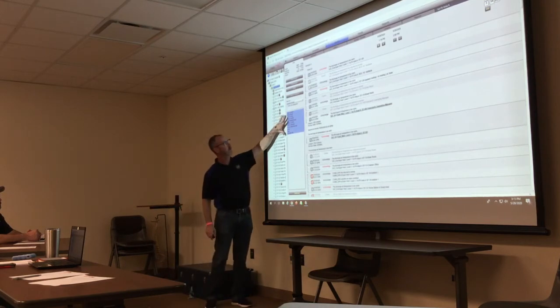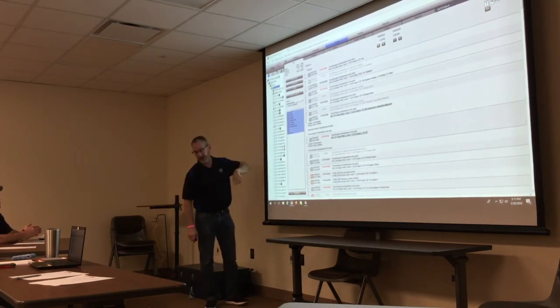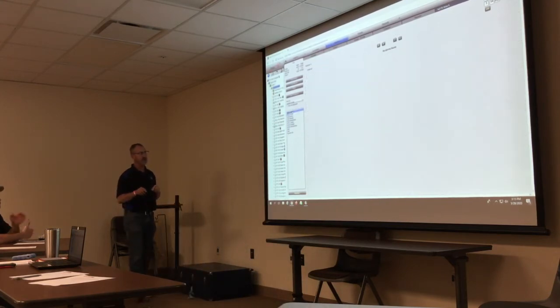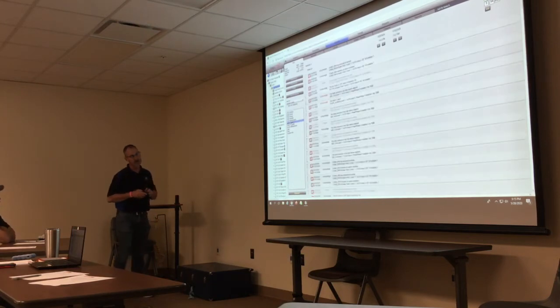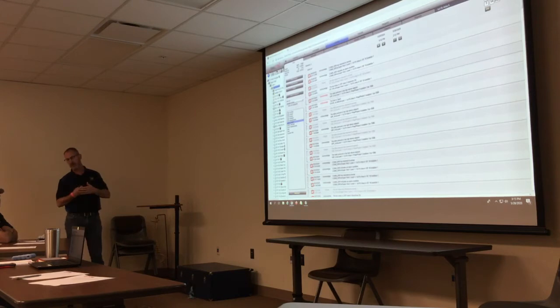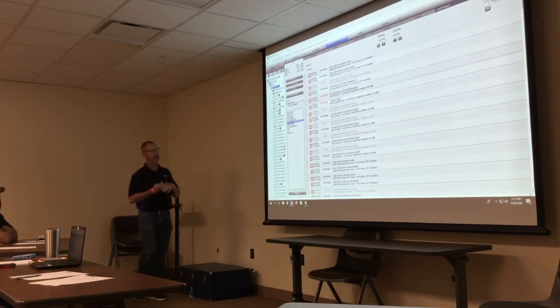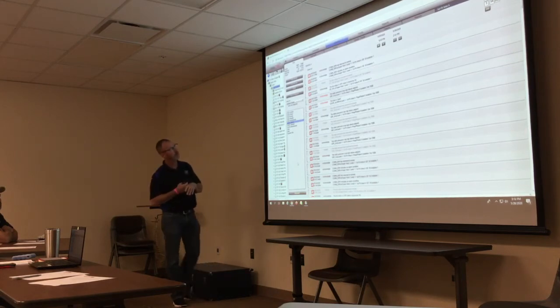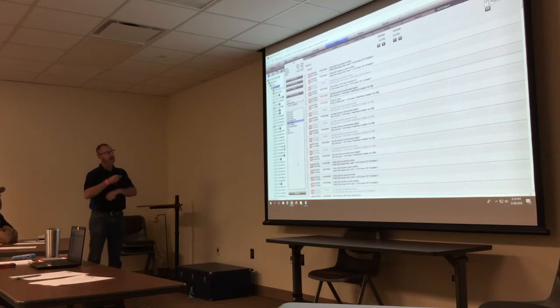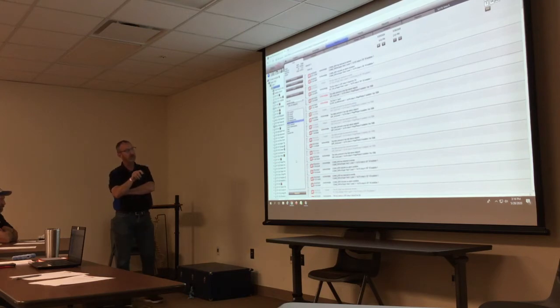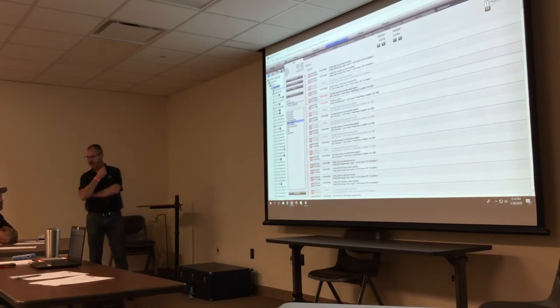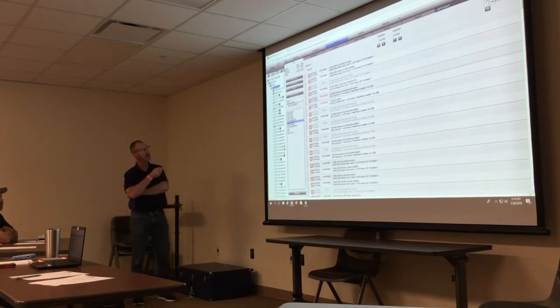Okay. Below the view by type, we actually can see what categories. If you're looking for specifically HVAC critical alarms, you can select that and see only the critical alarms that have come into the system. So you can filter out all the general, all the fault detection, those type of alarms. Okay. Any questions so far? If you knew you had a problem on Saturday, you want to go look at the alarms for a specific date, you do have a calendar that you can pull up. So you can search by time and date. Where is that located? To the top right corner of that action pane.